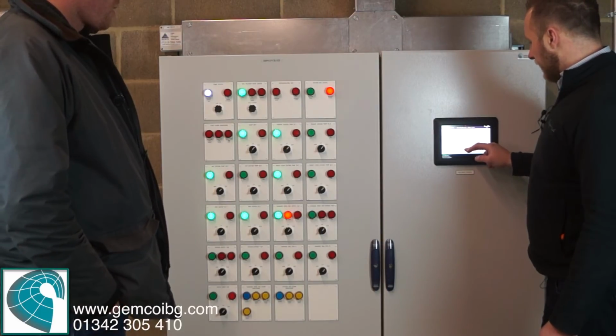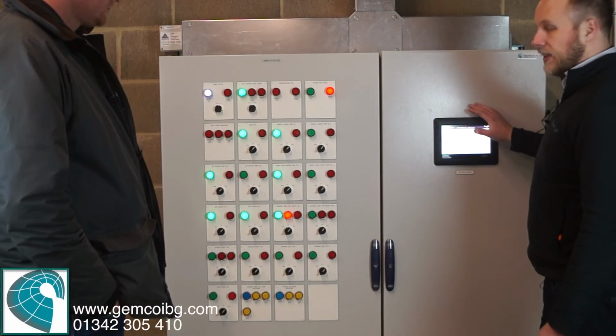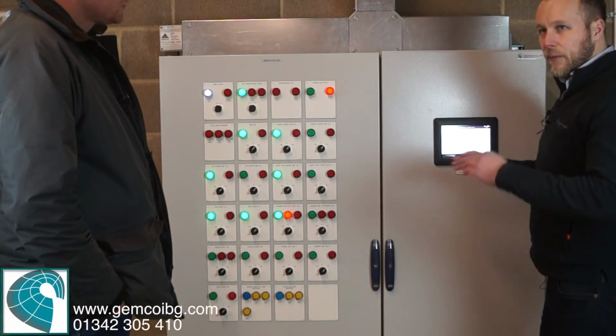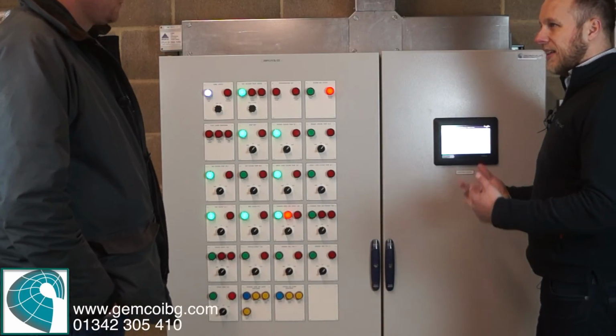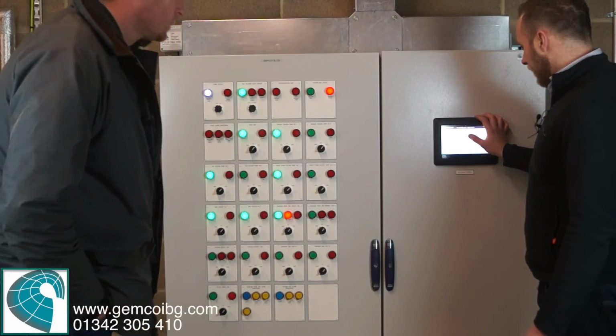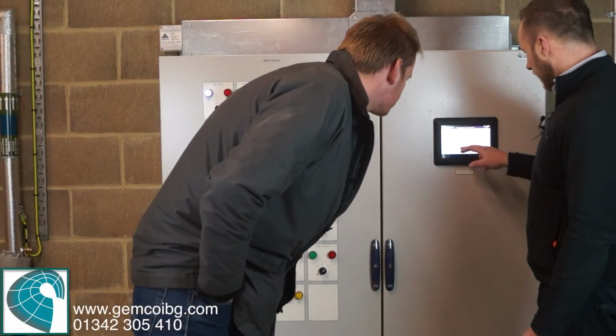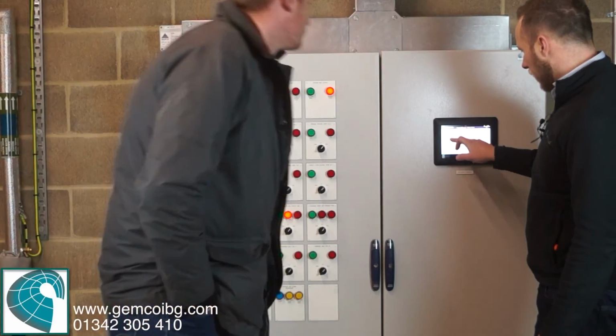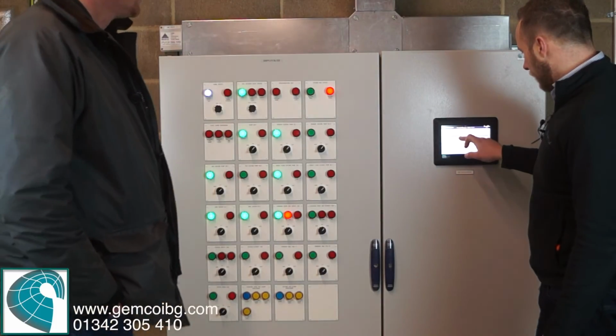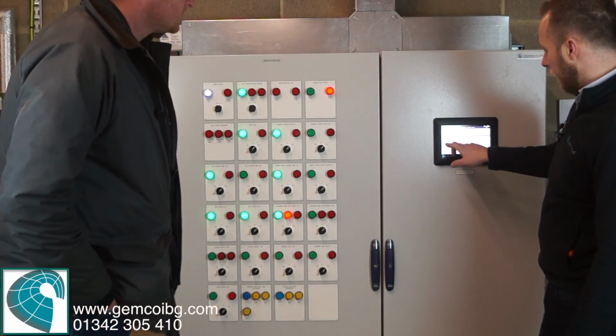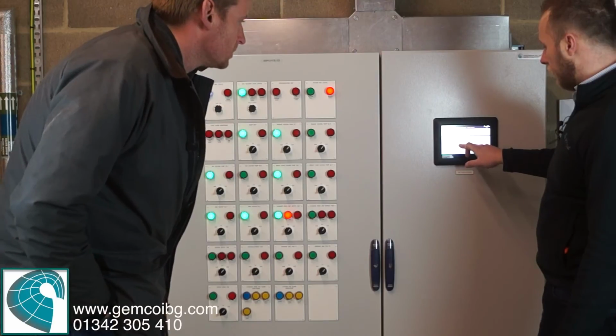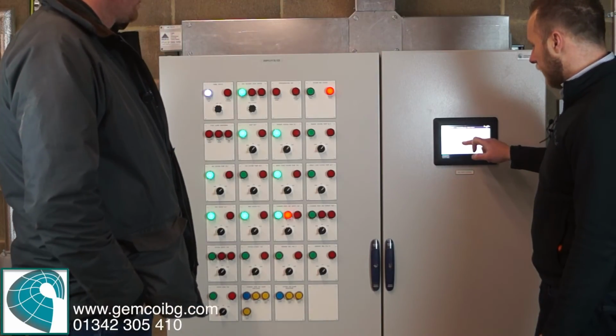Temperature settings, all of the frost settings you shouldn't be touching, because they're just conventional settings that have been tried and tested. How do you know they're the frost ones? They've usually got frost. So you've got outside frost set point, low pipe frost set point, internal space frost set point. They're the ones that I was talking you over.